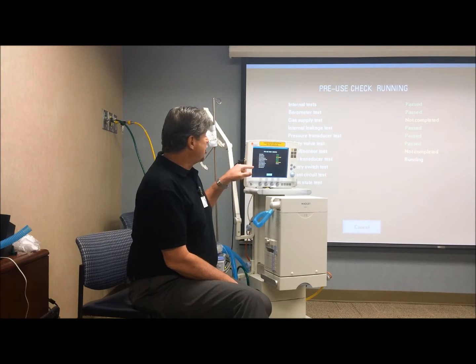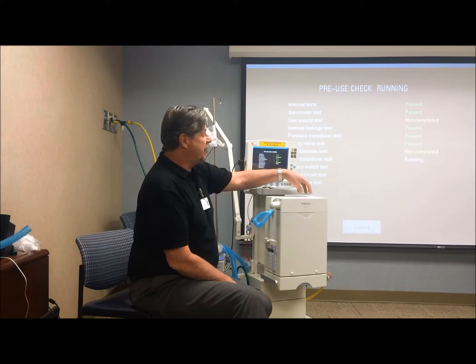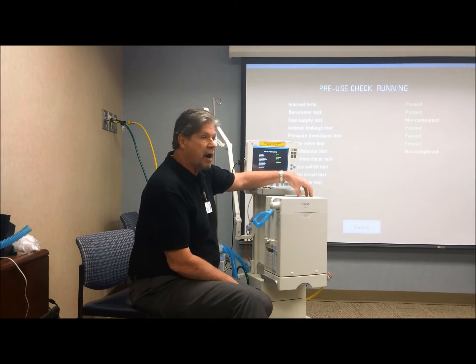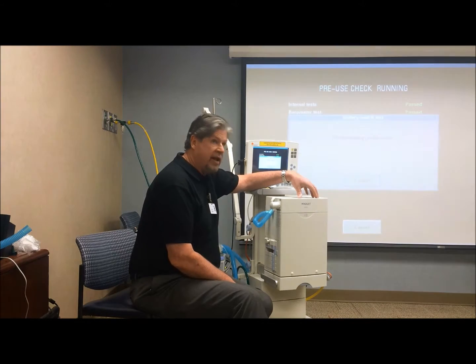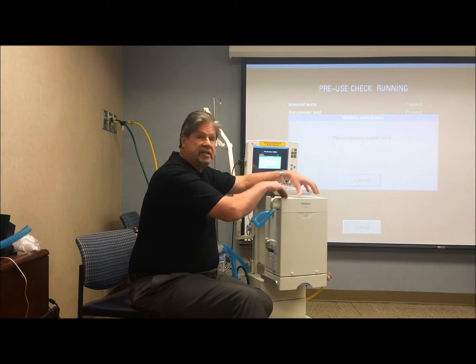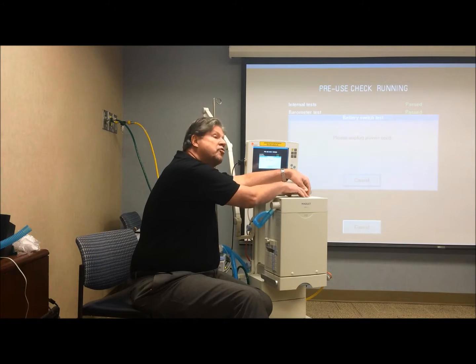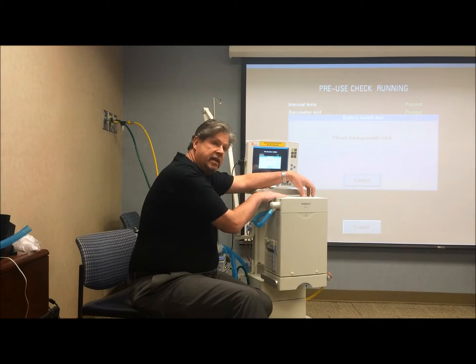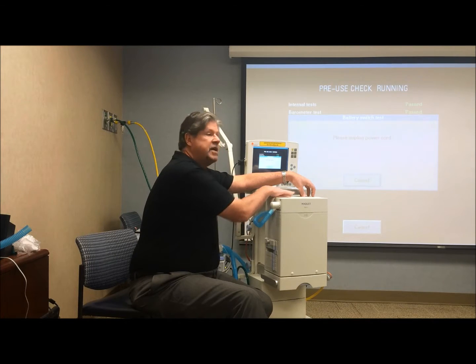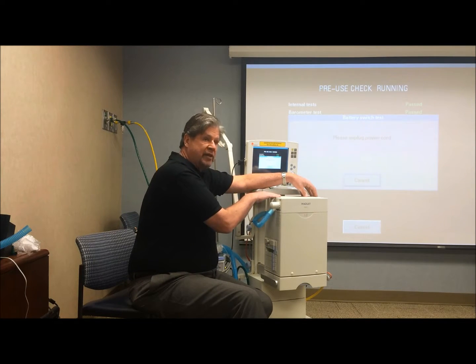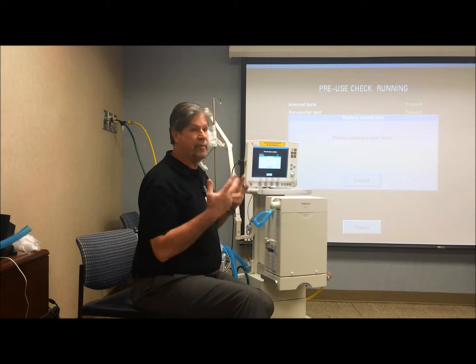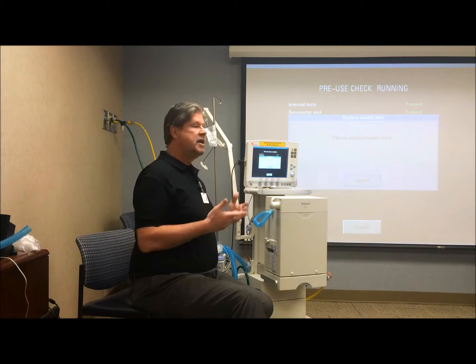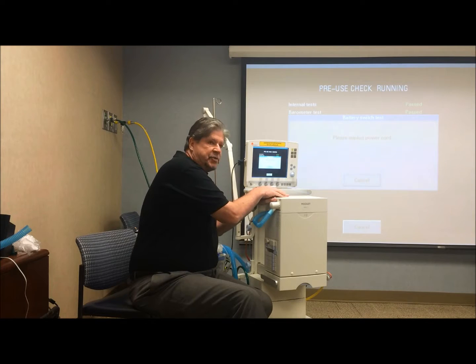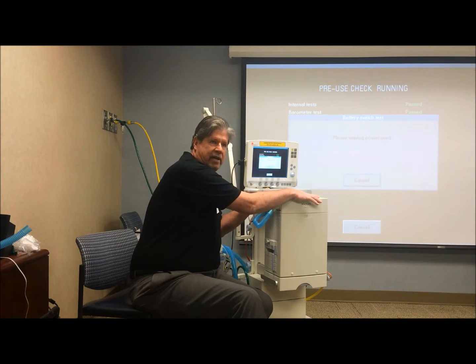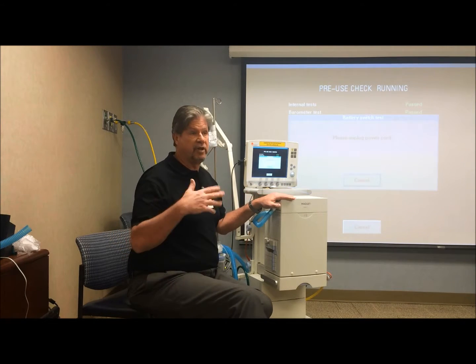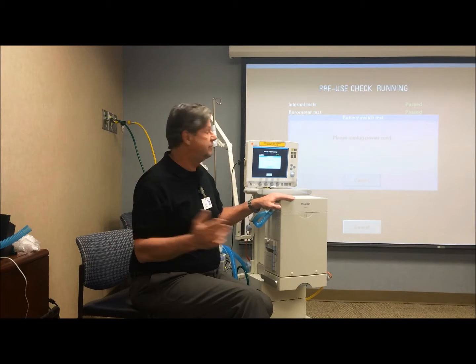So now the flow transducer test is occurring, and a lot of people think that if the flow transducer fails, it is the cassette. There's flow transducers in the gas modules as well. So if the gas modules' flow transducers fail, you're going to get a failed message on that particular item. So you don't know if it's the inspiratory side or the expiratory side, but there is a flow transducer in the expiratory side in the cassette as well.